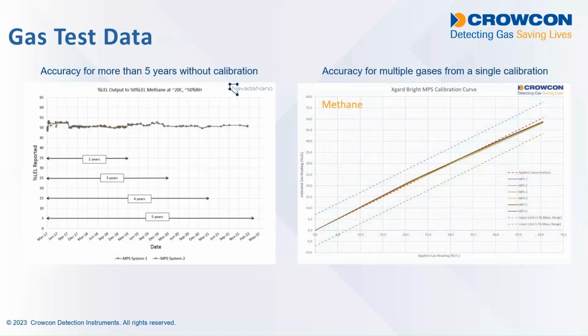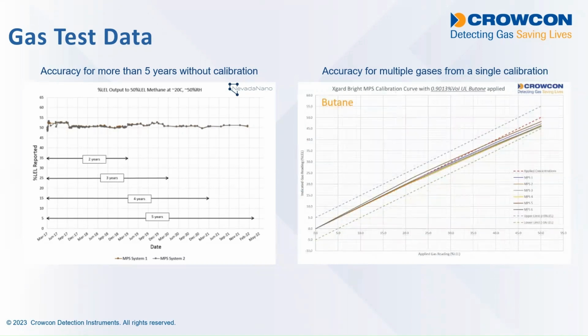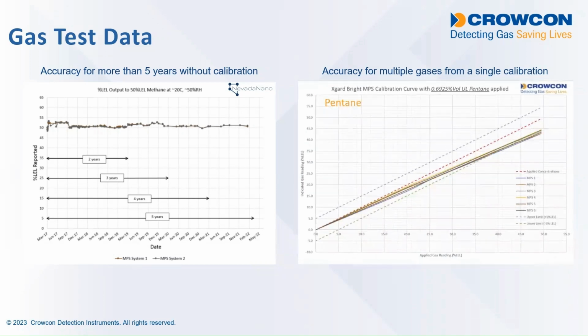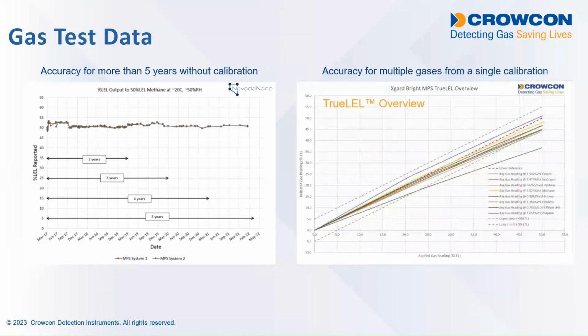And this is our test at Crowcon for the exposure to different gases. So with a standard methane calibration on the MPS sensor across 6 different detectors, you can see that they all read very consistently. The output from all 6 detectors are very tightly packed together for methane. And if the same sensors without recalibration are then exposed to butane, they're still very accurate on butane. The dotted lines above and below the response line are the limits of accuracy that are allowable in the European performance standards. So ethane, ethylene's a bit more challenging, hydrogen, LPG, pentane, propane. You can see across the spread of those 6 detectors, across the spread of all of those gases, they still remain very accurate just with that standard methane calibration.